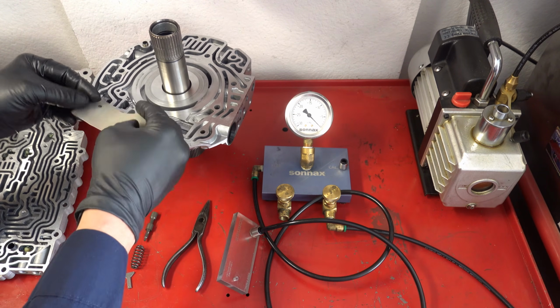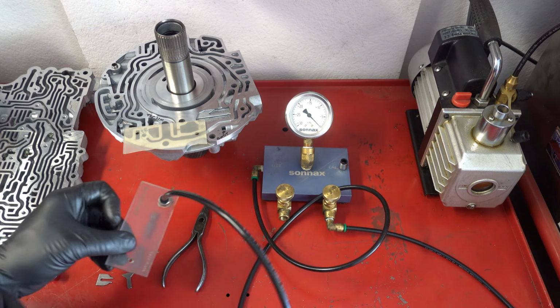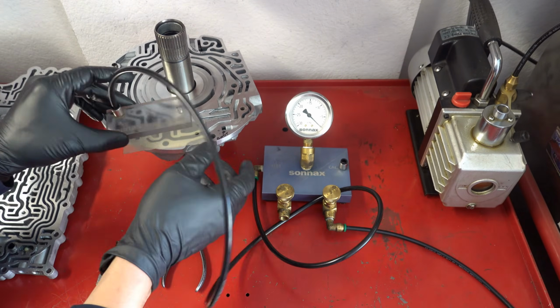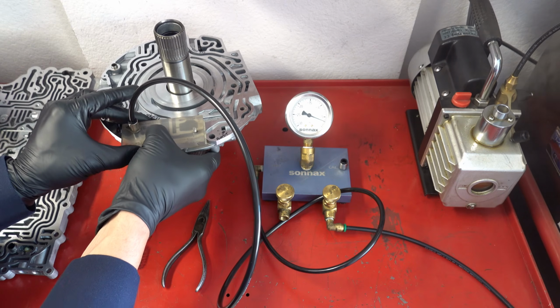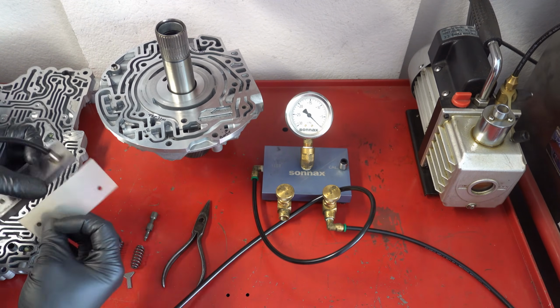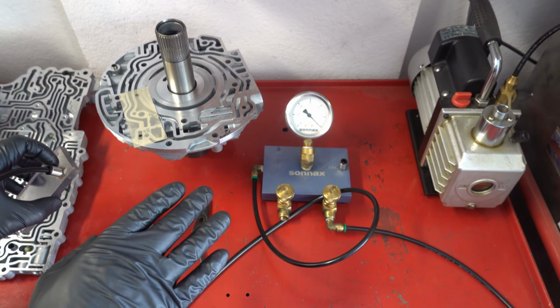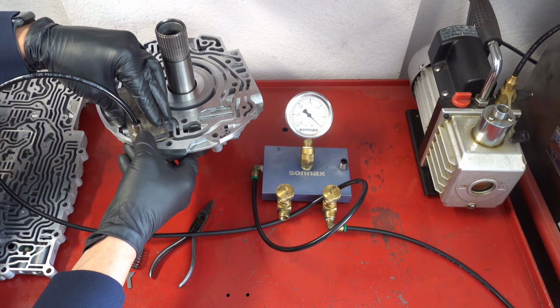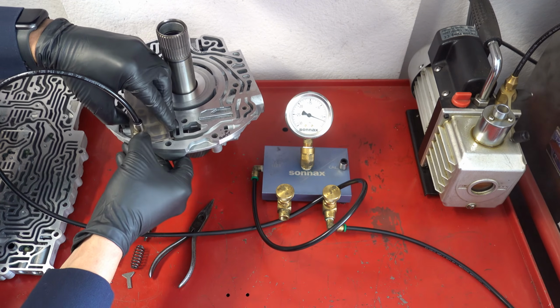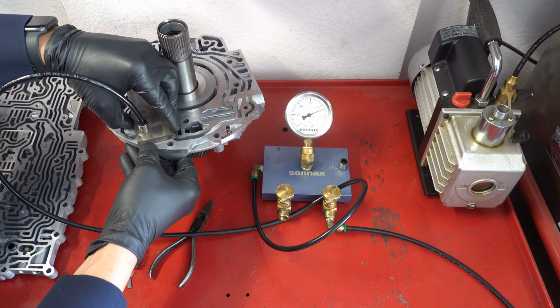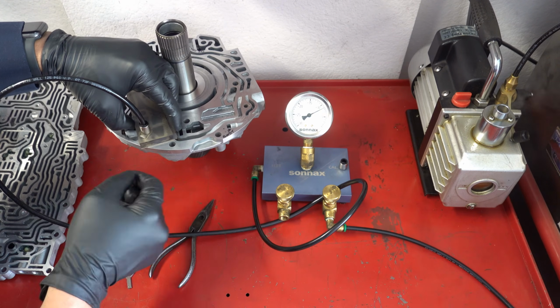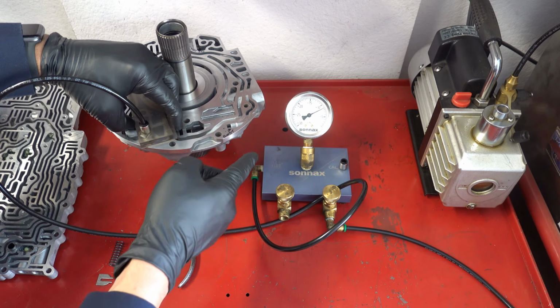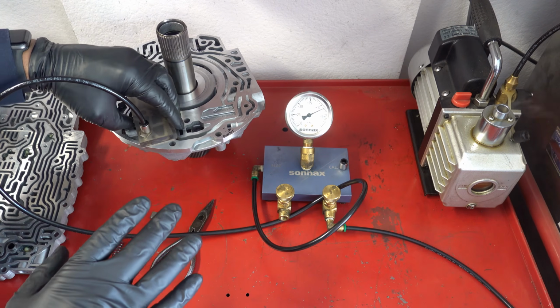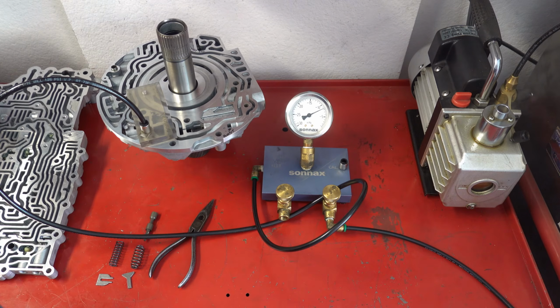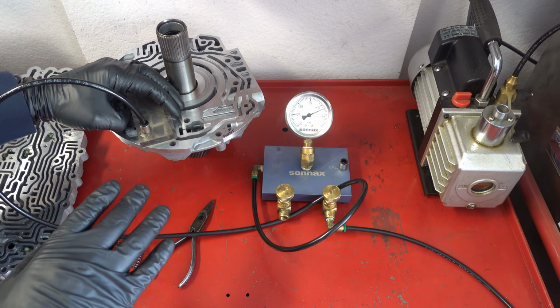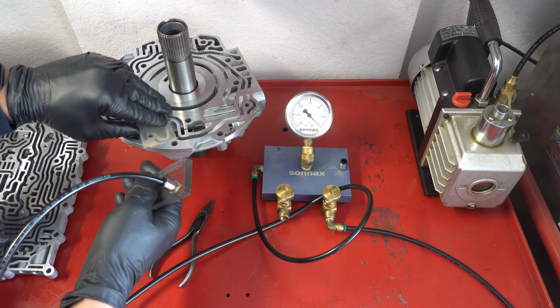Okay, so now we're going to test the main circuit, that rectangular port. A little awkward, trying to get it so that you can have an unobstructed view of the gauge. You may have to move the block over the cutout to make sure you're aligned. It's not very wide, but this is showing us 8 inches of mercury. And 8 inches of mercury is very weak for a pressure regulator valve or any hydraulic circuit. So obviously we know we'll need to take action here. And that's over the orifice.